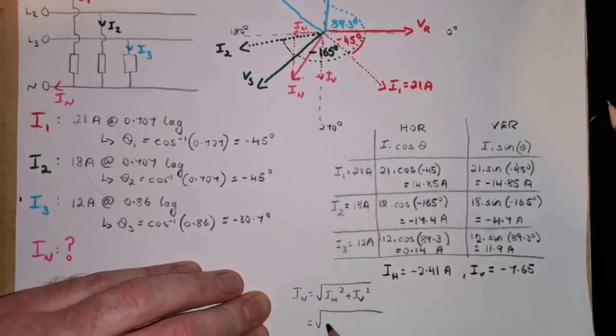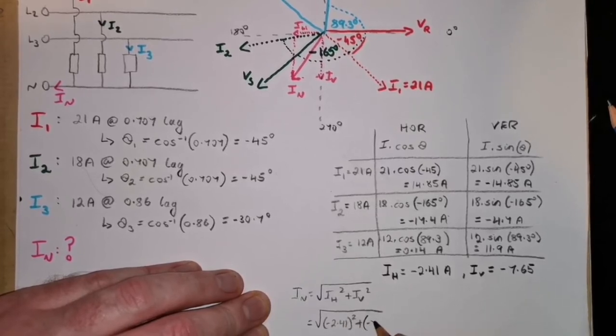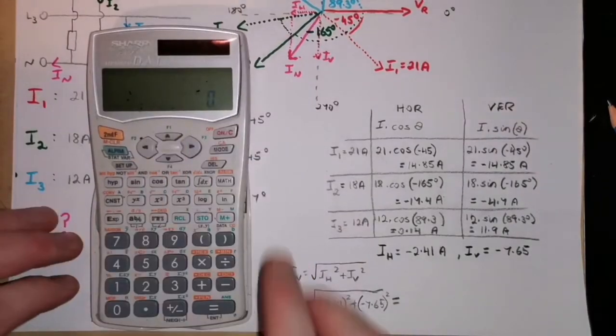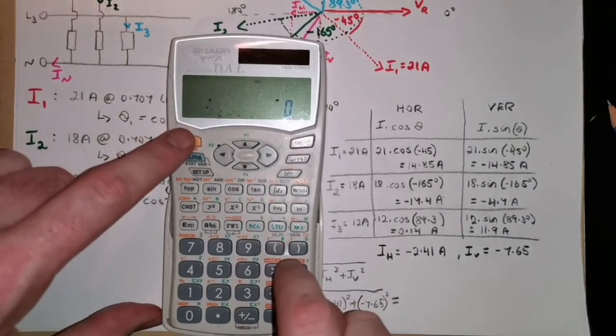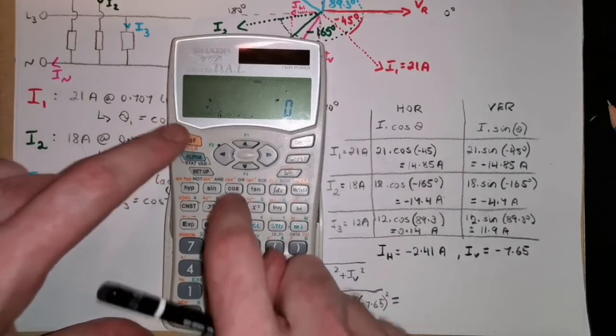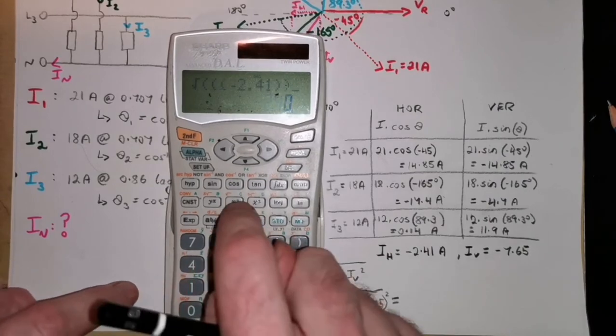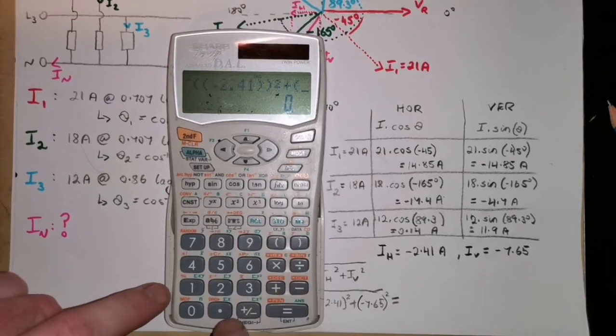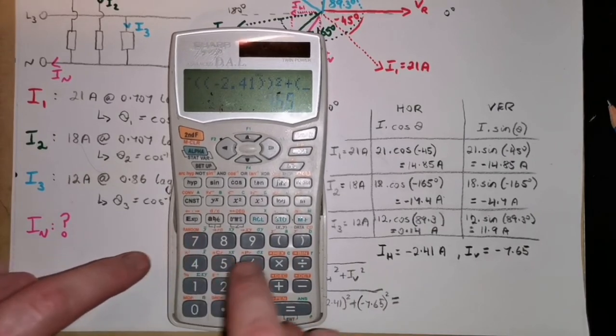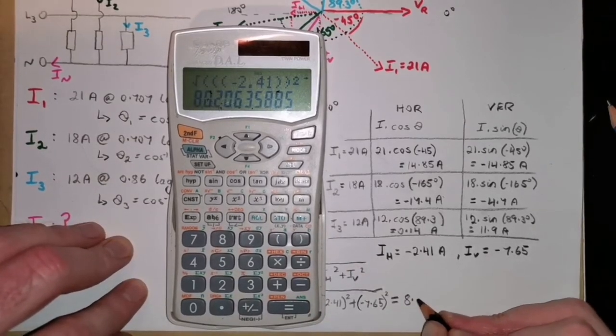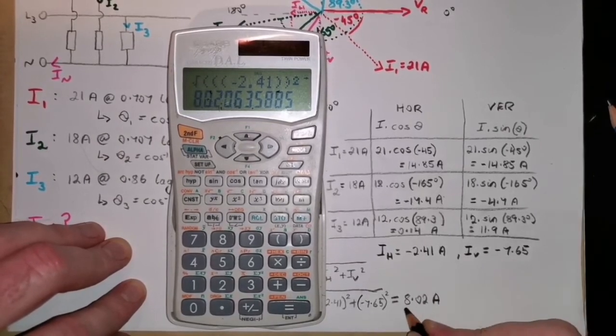Square root of minus 2.41 squared plus minus 7.65 squared. Now, to save space here, I'm going to put this calculation in one go, but you may not want to do that. It's up to you. So, the square root of minus 2.41 squared plus minus 7.65 squared. I'm getting about 8.02 amps, then, as my neutral current.